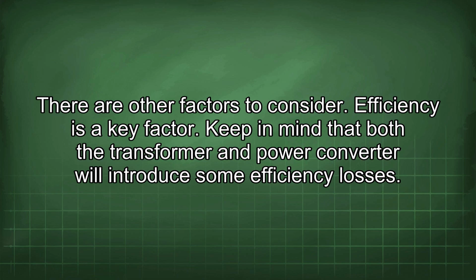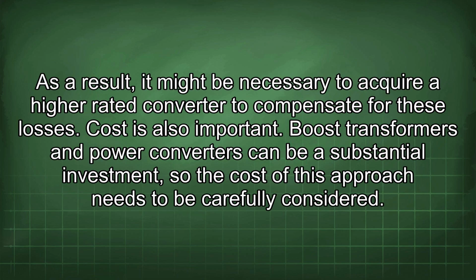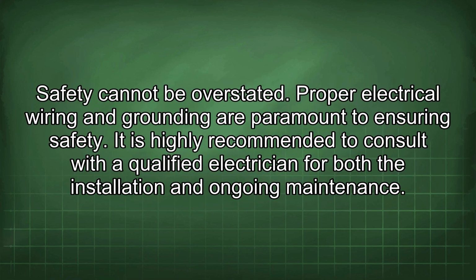There are other factors to consider. Efficiency is a key factor. Keep in mind that both the transformer and power converter will introduce some efficiency losses. As a result, it might be necessary to acquire a higher rated converter to compensate for these losses. Cost is also important. Boost transformers and power converters can be a substantial investment, so the cost of this approach needs to be carefully considered. Safety cannot be overstated. Proper electrical wiring and grounding are paramount to ensuring safety. It is highly recommended to consult with a qualified electrician for both the installation and ongoing maintenance.